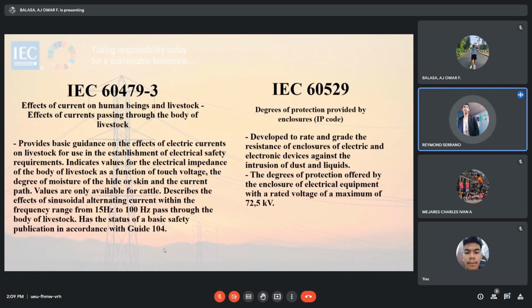So next is IEC 60529, degrees of protection provided by enclosures, the IP code, developed to rate and grade the resistance of enclosures for electric and electronic devices against the intrusion of dust and liquids. It covers the degrees of protection offered by the enclosure of electrical equipment with a rated voltage of a maximum of 72.5 kV. The degrees of protection provided by the enclosure of electrical equipment are required to protect persons against access to hazardous parts inside the enclosure and to protect the equipment inside the enclosure against ingress of solid objects.